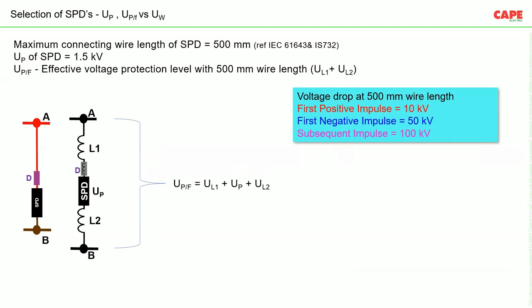So the voltage drop across 500 mm wire length, in case of first positive impulse, will be 10 kV. As we have earlier seen, 20 kV was for 1 meter of wire length. So for half a meter of wire length, the voltage drop will be 10 kV. First negative impulse will have a voltage drop of 50 kV. We have seen that for 1 meter it was 100 kV, so for half a meter it is 50 kV. For subsequent impulses, for 1 meter it was 200 kV. So for half a meter of wire length, which is the standard recommendation, it is 100 kV.